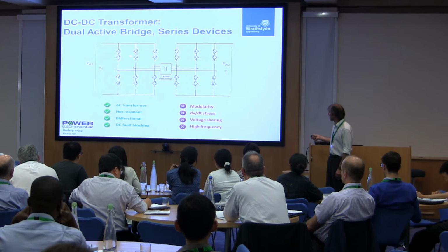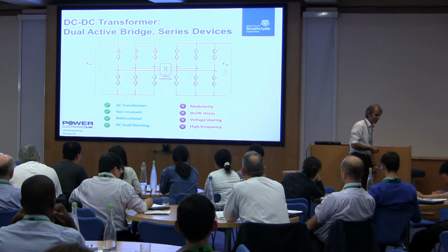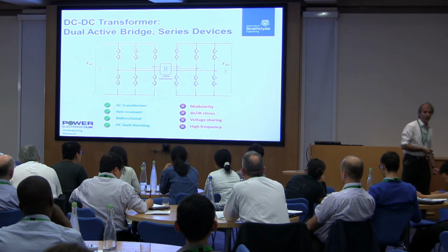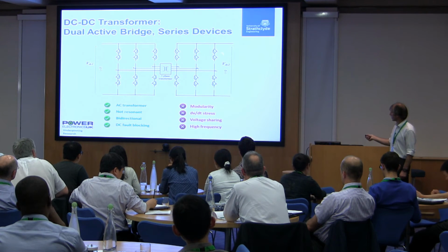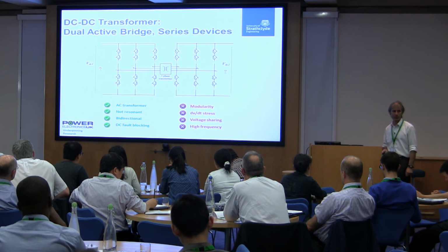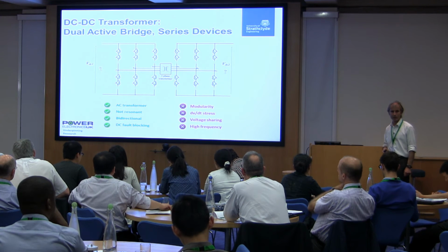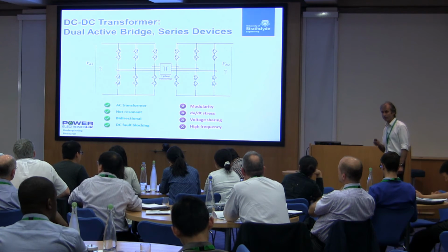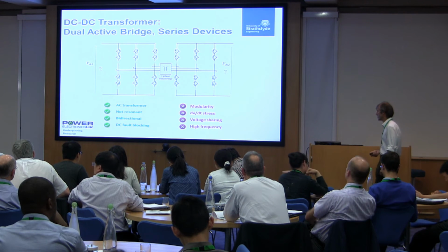Problems - the principal one is losses. On the previous diagrams we showed the DC to AC converter block as part of the conventional AC collection network, and we replaced it with a DC to DC converter block. It's actually got twice the number of devices and therefore potentially twice the losses compared to a conventional DC to AC conversion stage.